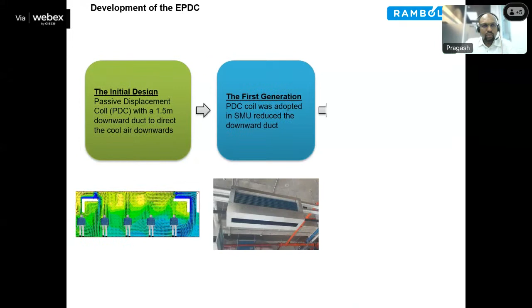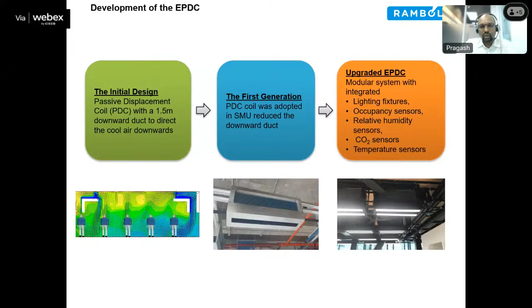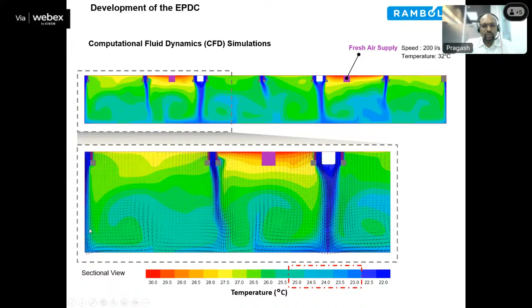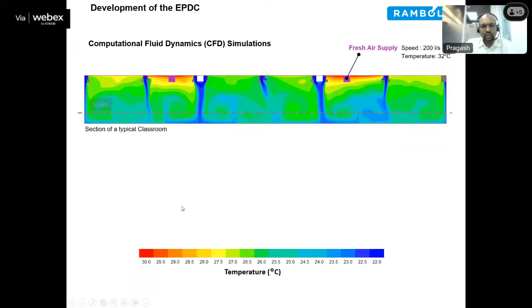So this is the final product. What you see is, the initial design had a very long down duct, and then we reduced the down duct with optimization, and we minimized it to about 200 mm of space, which is sufficient to bring the cool air to the occupied zone. That's the final product. As I mentioned earlier, the fresh air is just discharged near the coil. You can see the red color is the hot air discharged at about 30 to 33 degrees, and it is cooled down before it comes to the occupied zone. At the ceiling level, of course, the temperature is higher than at the occupied zone. You can see we achieve the desired temperature that we need.